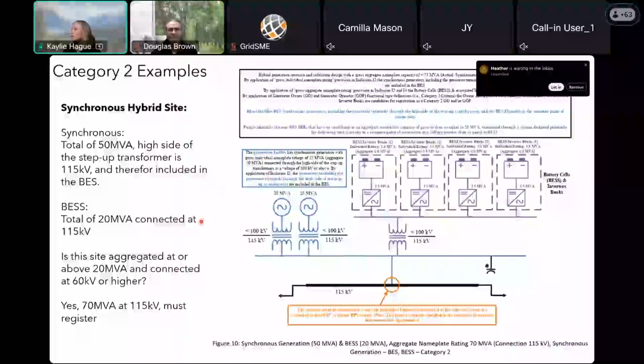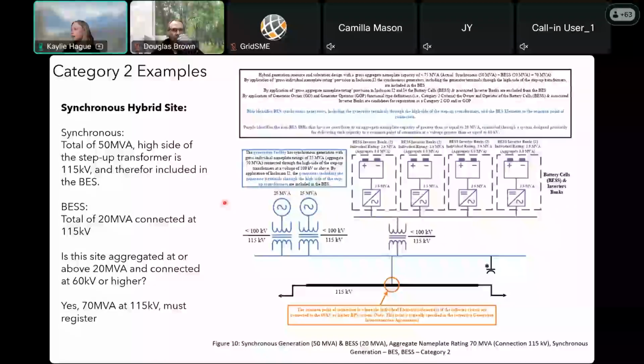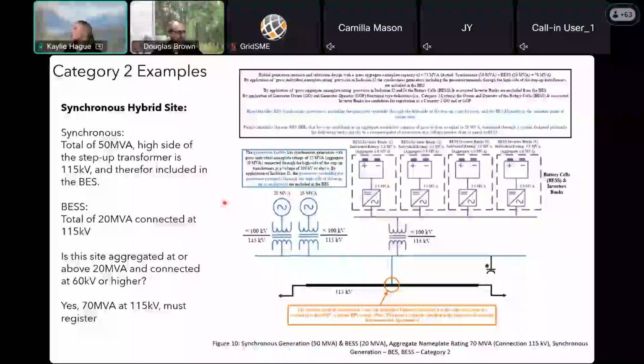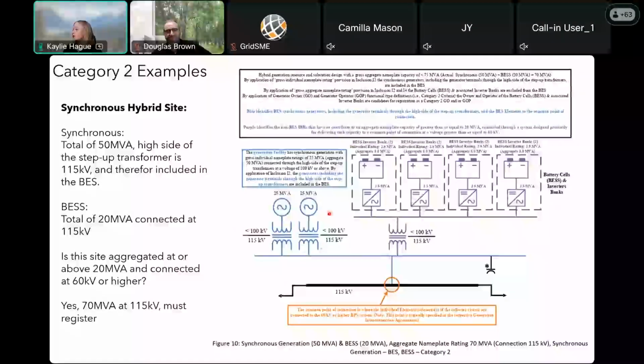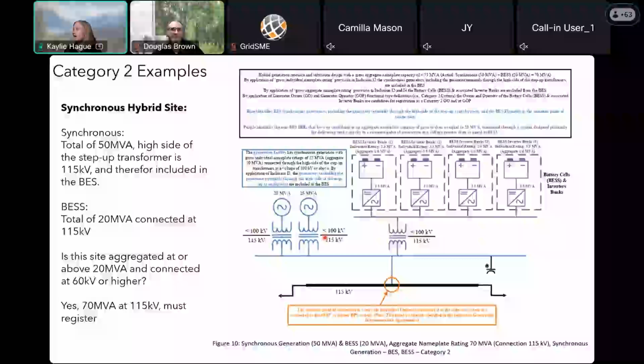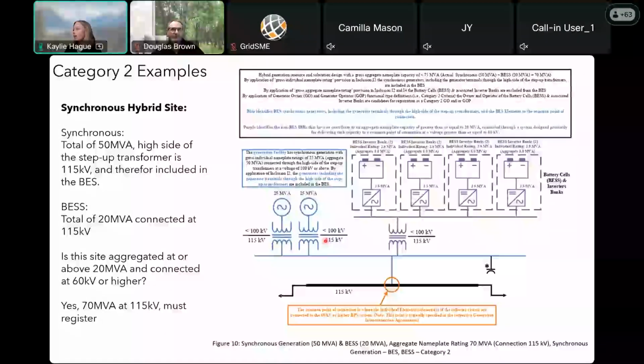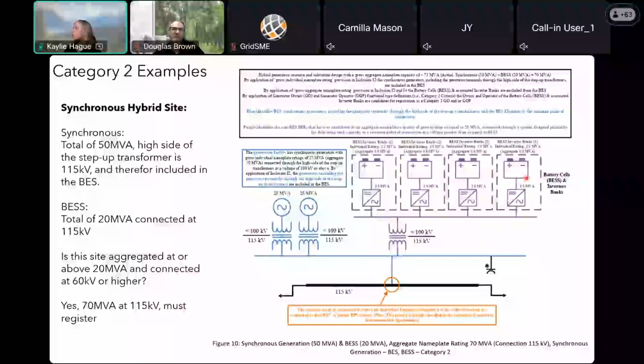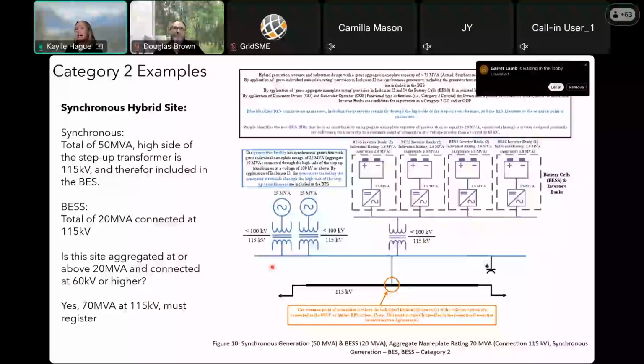All right, next example, we're going to throw some synchronous generation in here with your GO-IBR. So remember, synchronous generation is not considered an IBR resource, but there are situations where you might aggregate together. So we'll take a moment to look at that. This blue side over here is your synchronous generation for a total of 50 MVA connected on the high side at 115 kV. So this is already a bulk electric system qualified site. And then if we look over here at the IBR side, we have 2, 4, 6, 8 BESS inverter banks individually rated at 2.5 MVA. So that will give us 20 MVA, and they are connected at 115 kV. So together they're aggregating for a total capacity of 70 MVA and connected at 115 kV. So yes, you must register.